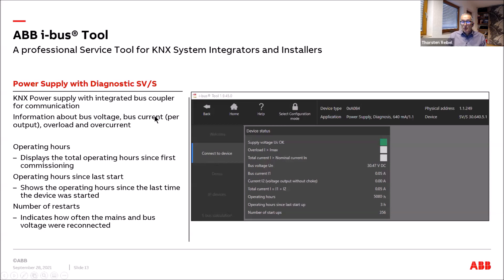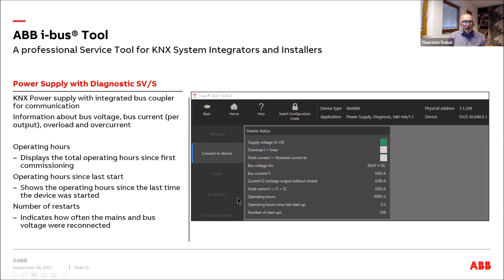For the KNX power supply with integrated bus coupler, the tool provides diagnostic information: bus voltage and bus current per output — for a device with two outputs — plus status information such as overload or overcurrent. Three especially interesting features are: total operating hours (in this example, 5,080 hours), operating hours since last start, which shows when a power failure occurred, and the number of restarts.